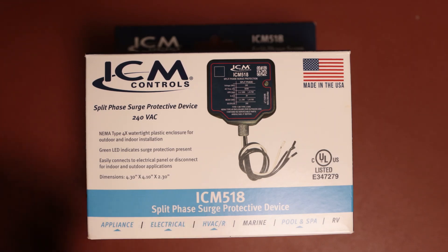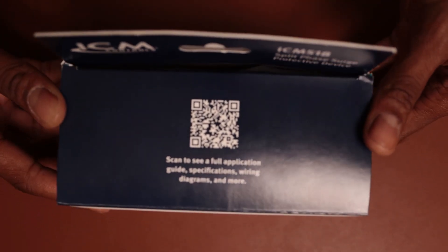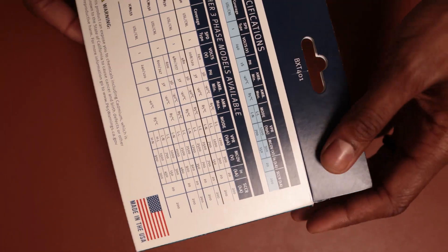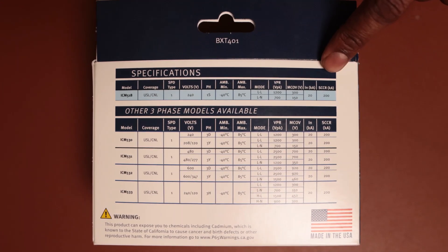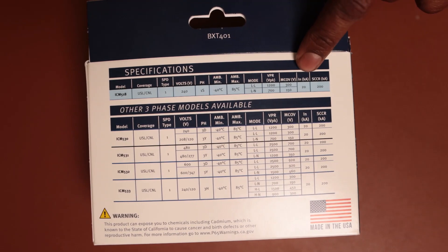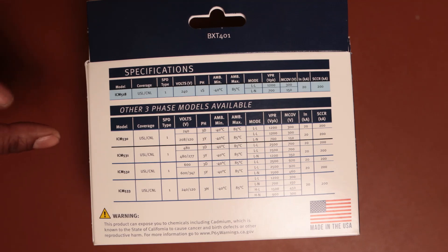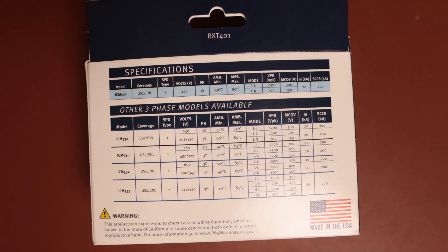This is the ICM 518 model. One of the best parts about it is that it's made in the USA. On the back it shows the specs of the device. One of the most important specs is the short circuit current rating, which is rated for 200,000, and the In, which is rated for 20,000. They also have other models for three-phase applications and some other applications.